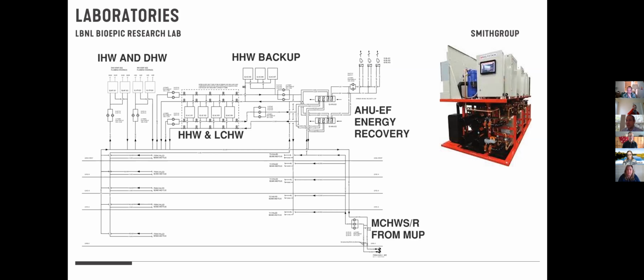That's a really important strategy for labs. Labs that see high air changes have exhaust air that's a phenomenal source to grab energy from, whether through a traditional runaround loop as a heat recovery coil, or through a heat pump using more active heat recovery.